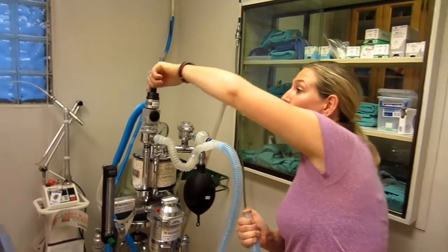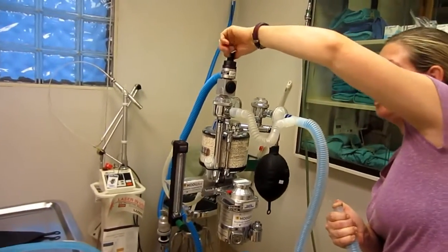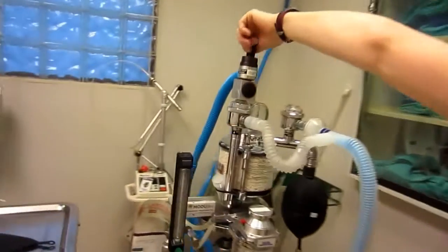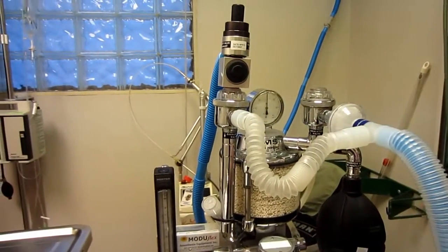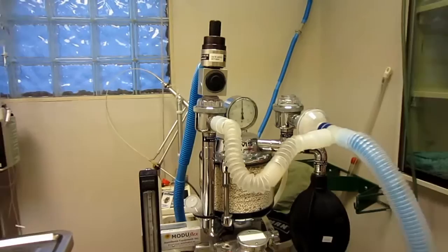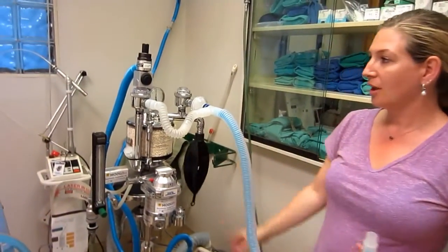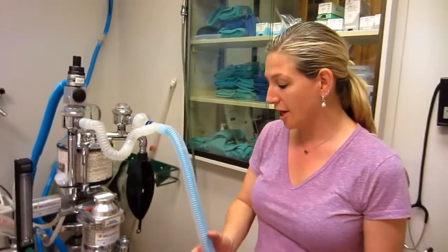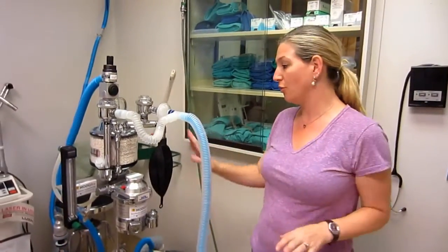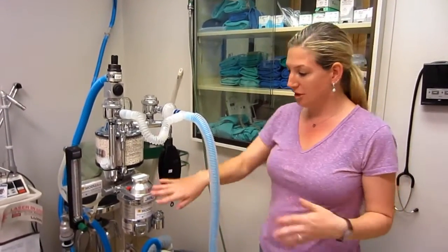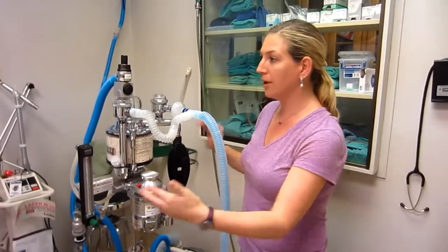And now I'm going to open my pop-off valve. And you can see, as soon as it's open, that goes back to 0. All of that went out the exhaust, and this is pretty empty. So that would be how you check for pressure. Make sure there's no holes in the bag, there's nothing left on or open.